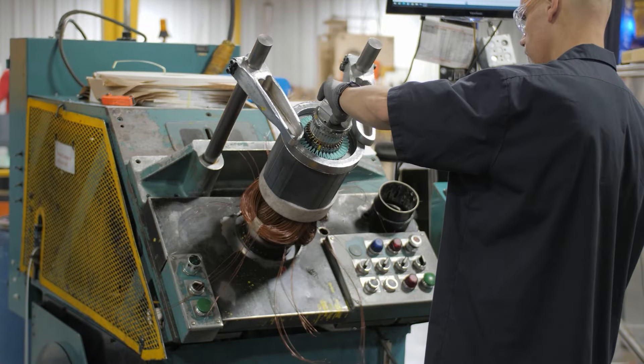But what is IEEE 841? IEEE 841 began as a recommended practice in 1985 and became a standard in 1994. The current version was published in 2021. IEEE 841 allows petrochemical companies and other industries with critical applications and harsh environments to have readily available quality TEFC motors.